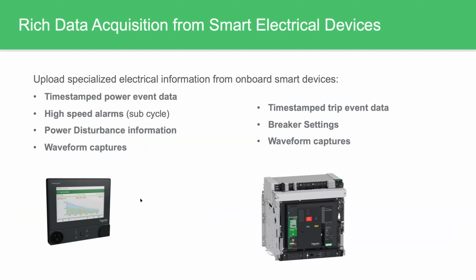On the slide here, you'll see things like power quality meters. These specialized devices have time-stamped power event data, so they're time-synced throughout the entire system. They have onboard data logging and data processing, and provide high-speed sub-cycle alarms, capable of sampling at thousands of samples per cycle. They offer power disturbance information and waveform captures, so visibility to things like voltage sags and swells, harmonics, and the ability to pinpoint when and where an event occurs in the system.